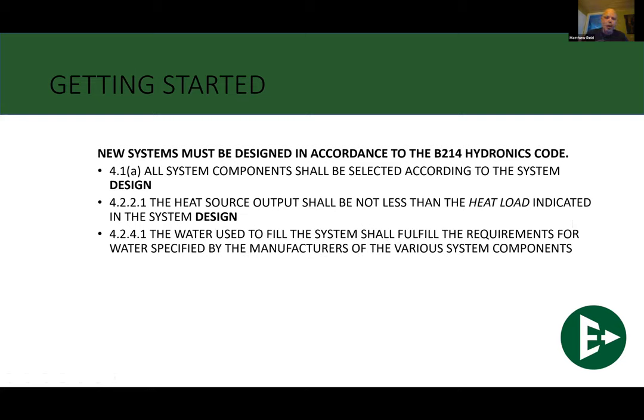This is important. The water used to fill the system shall fulfill the requirements for water specified by the manufacturer of various system components. We're going to be going over this here in the end, but lots of manufacturers will outline what water quality they require. They talk about total dissolved solids. They require between 50 and 200 parts per million of these total dissolved solids. They have a pH level that they require to go into their systems. So that's going to be pieces that we're going to be talking about when we get into the water quality side of it. These are required by the manufacturers.